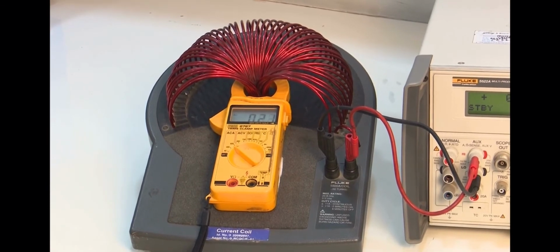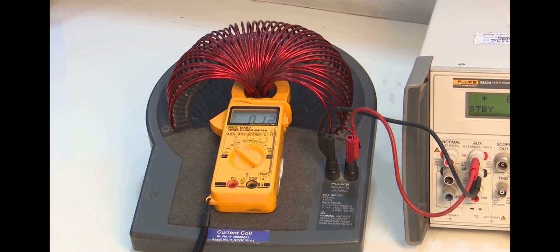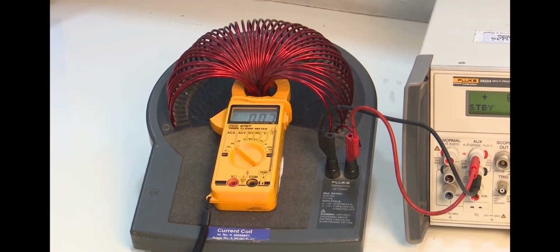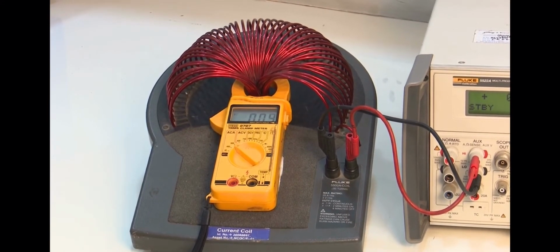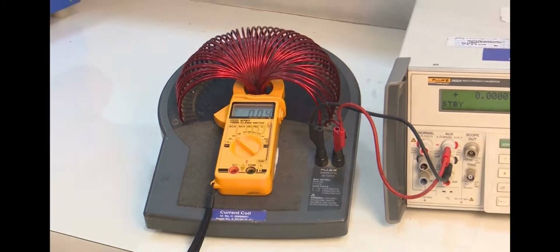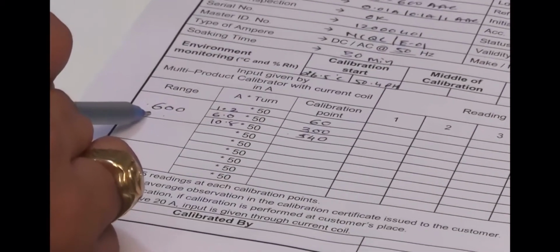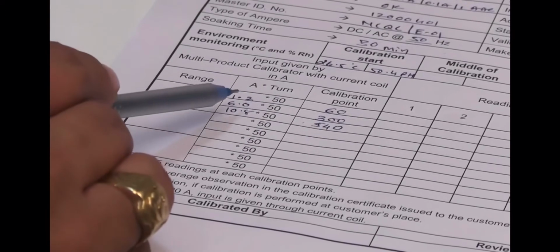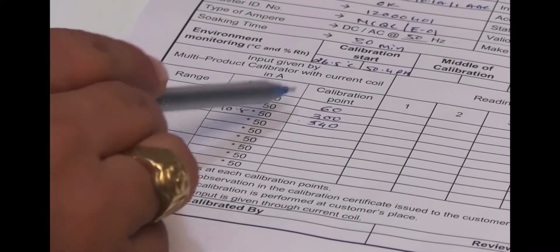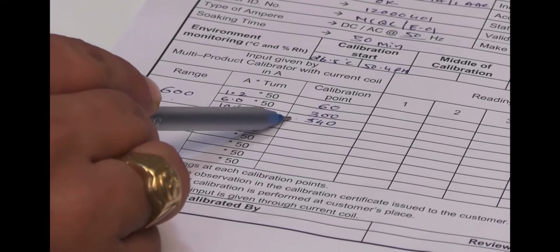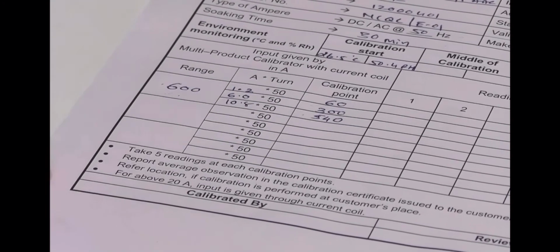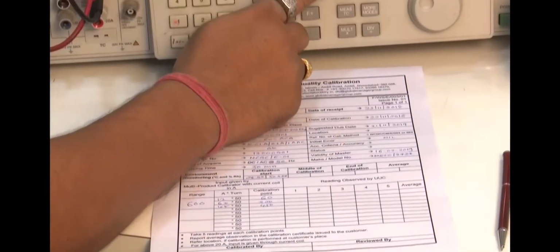Now I am going to demonstrate the calibration of ampere range. As per calibration method for calibration of clamp meter, we need to select calibration points as 10%, 50% and 90% of ampere range of clamp meter as unit under calibration. Here I will calibrate 600 ampere AC range. So calibration points will be 60 ampere, 300 ampere and 540 ampere. Now I am proceeding for calibration.